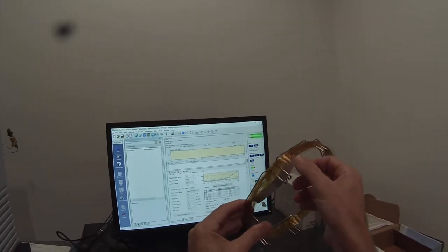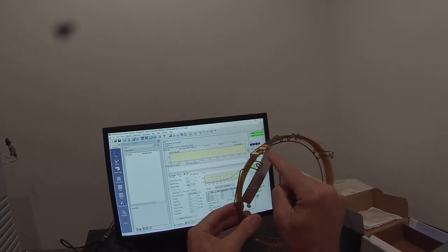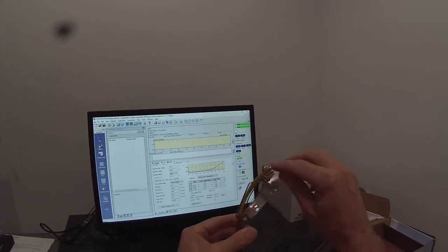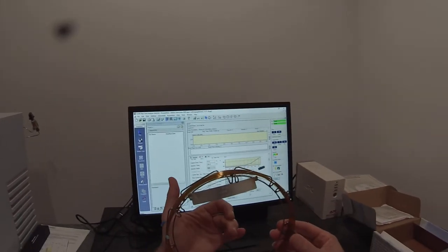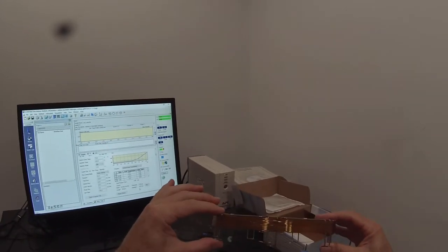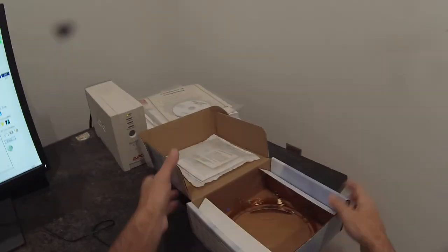What that column looks like is 30 meters of glass capillary that's wrapped around. This is a different column. And so the inner diameter, the inside of this tube, is 0.25 millimeters across. And it's then spun glass that's kind of hung in there so that it's inside the oven. So it's kind of a marvel of engineering that you could get a uniform 0.25 millimeter inner diameter over 30 meters of glass column and then coat that with 0.25 micrometer thick stationary phase, which is the silicone, the polysiloxane. It separates mostly on boiling point. Not much polarity in that silicone.